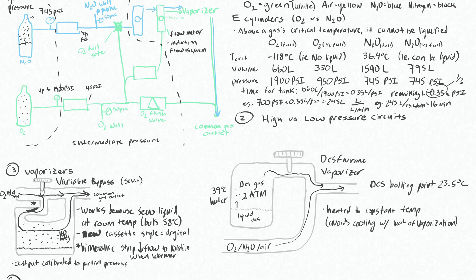Des vaporizers on the other hand output the set percentage, or they're calibrated to percent. Whether you are at sea level or you are on top of a mountain, you set this dial to two percent - or you would set it to six percent if you're using des which would be more reasonable - it is always going to be outputting six percent.